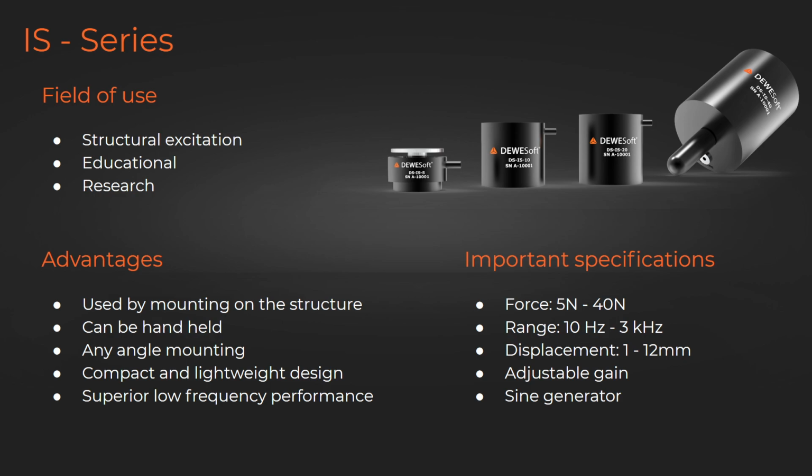Important specifications are the force range from 5 Newton to 40 Newton, the frequency range from 10 Hz to 3 kHz. They have displacements from 1 to 12 millimeters. They have adjustable gain, and they have the internal sine generator.